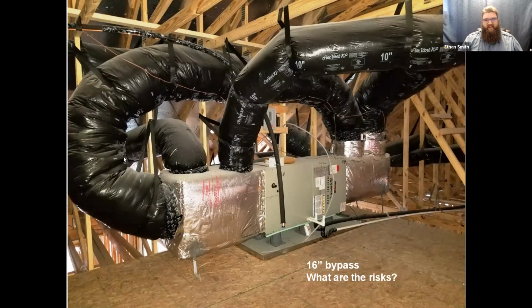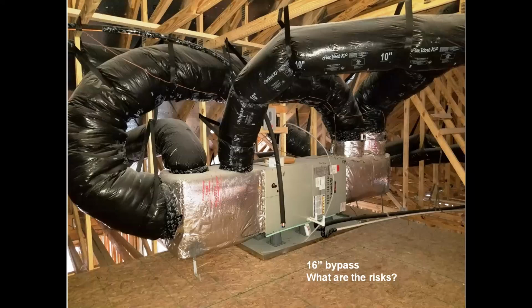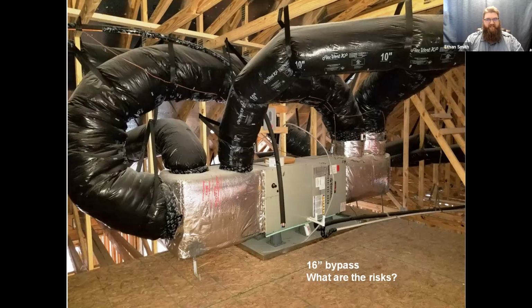That is a 16-inch bypass. What do you think is going to happen to that thing? So getting short circuited. It's going to short cycle in cooling. It's going to short cycle in heat. I mean, this is an electric air handler, guys. They're probably going to throw a 20 kW heater in here. Needs 1800 CFM on a 16-inch bypass. Thing's going to melt down.